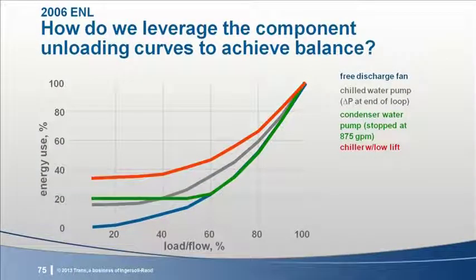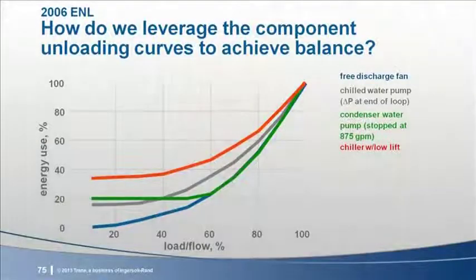Let's see what this might look like. I'm sure you still remember this chart of unloading performance we showed earlier. I suggested it represented balance control for an imaginary set of conditions and would result in efficient system operation. Let's see what unbalanced operation might look like. What if we set the condenser pump to provide design flow and the cooling tower fan set point at 55 degrees? On this chart, we can actually see what would happen.